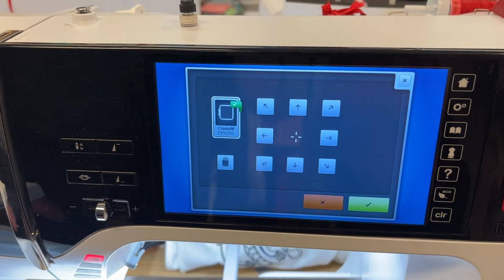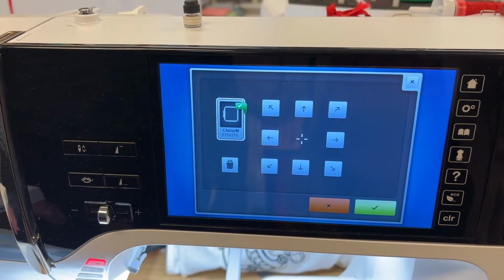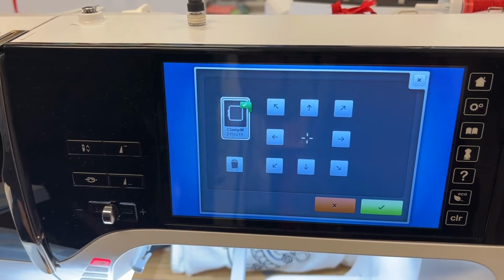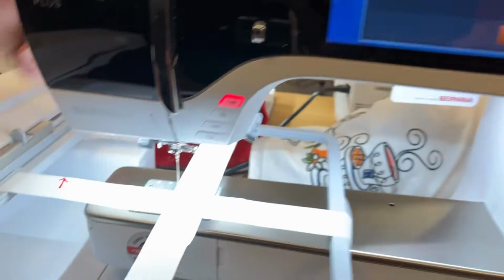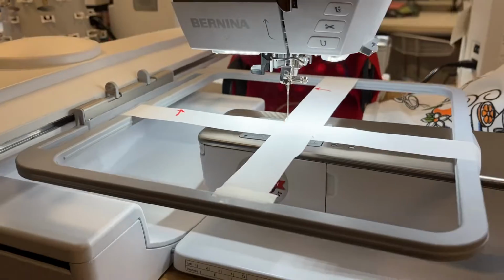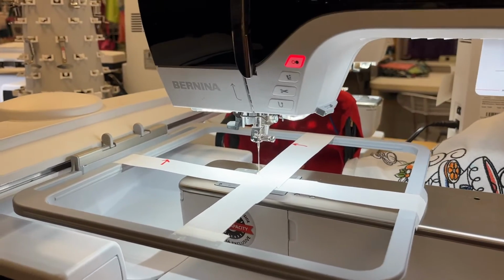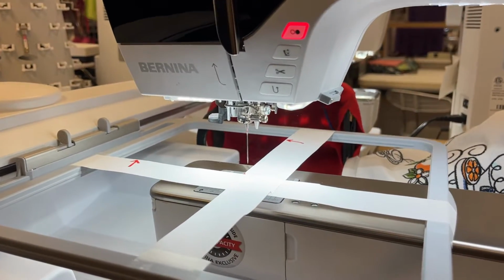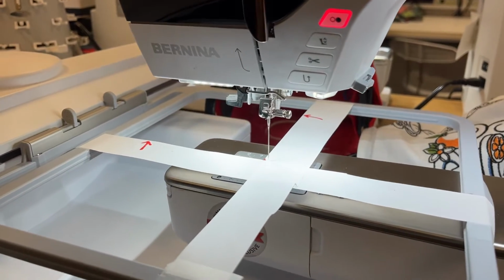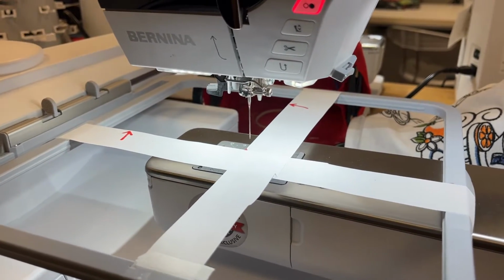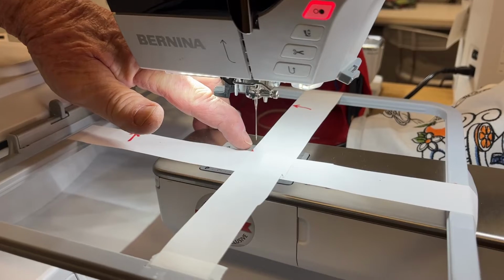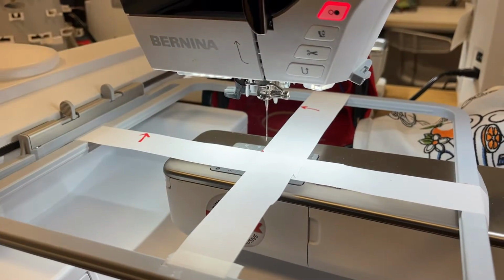The first thing I do is inspect to see if I'm at exact center. If we look close down here and I rotate the needle down, I'm nowhere close to center. This is what the calibration is for - we need to calibrate that needle right to the little red mark I made, right to this opening. You want that needle to kiss both sides of that paper.